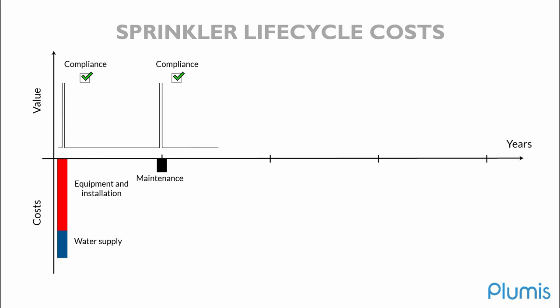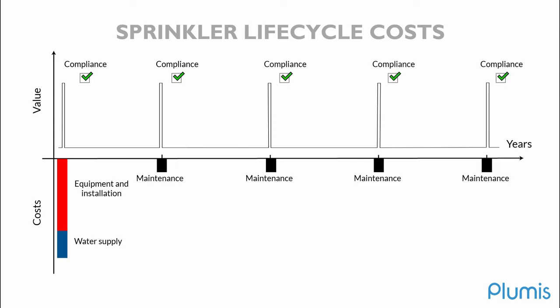Then a year later, you'd have another maintenance check. This is the industry standard annual compliance checks. And every time that you did this, you would also get another confirmation that the system would be tested and verified that it is ready to act. Now, the difficulty or the problem with this is that if a minor fault is introduced in between these maintenance checks, then it's not necessarily going to get picked up until the next maintenance cycle.